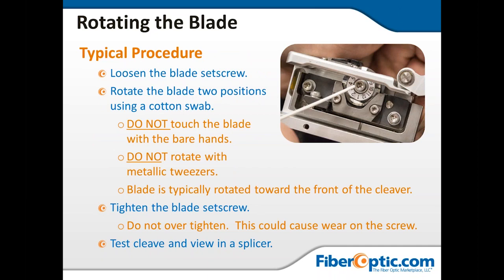Typical procedure, rotating the blade. You'll see it: loosen the blade center set screw. Rotate the blade two positions using a cotton swab. Do not touch the blade with bare hands. Do not rotate with metallic tweezers. The blade is typically rotated towards the front of the cleaver. Tighten the blade set screw. Do not over tighten. This could cause wear on the screw or stripping it.